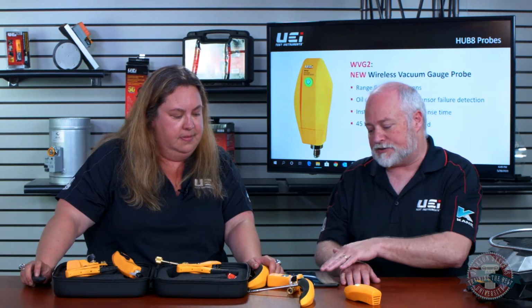The other thing that's in there, you can set an alarm. So if you want to know, hey, I've held a 500 micron vacuum for 20 minutes, I can set that. So now I know that I've held it, I haven't just hit 500 microns and I'm done. No, we need to hold that for a little while and make sure we've got all that moisture out of the system. Excellent. And as promised, I did say that we would circle back to that original picture.